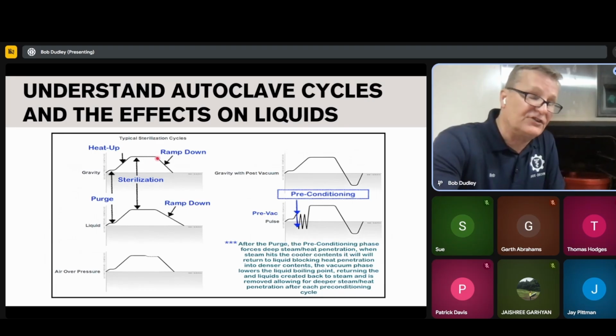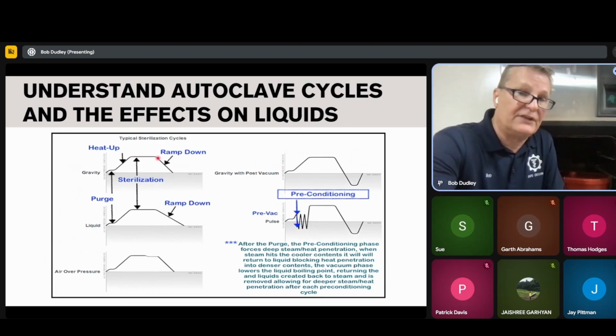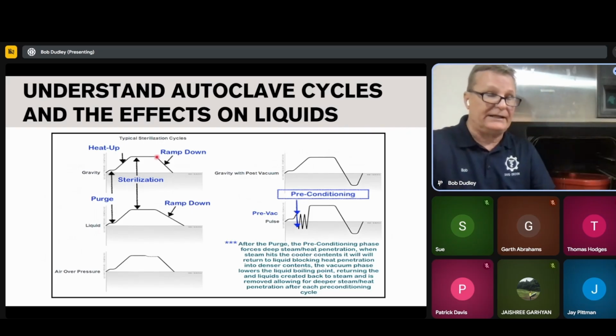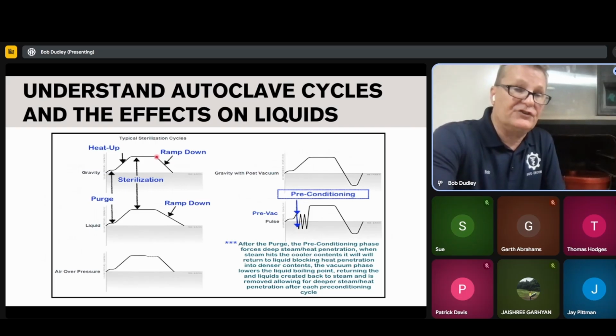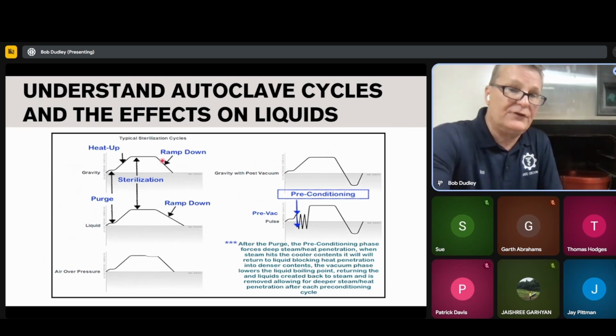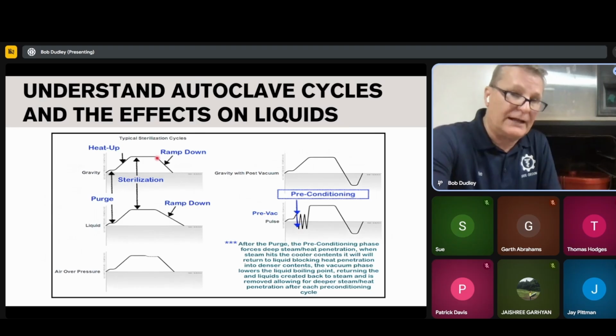Now, the gravity cycle is exactly what it is. When you're finished with that sterilization part of this, what generally happens is it says, okay, sterilization complete, everything is good, and it's going to shut off the steam, and then it's going to open your drain valve, and then there's an air inlet, filtered air inlet valve, and it's going to ramp down. So if you have any liquids and your boiling point for your liquids is 123, and then within 45 seconds it's going to go down to 14 inches, you've just created a volcano, a Mount Kilauea type of thing, where that water is all gone.